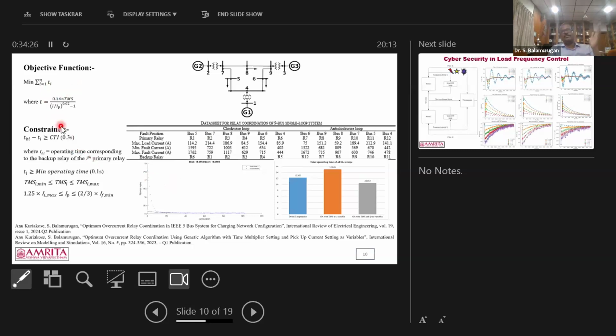So here also we can use an optimization problem. Here our objective function is the primary protection and the backup protection. The total time taken for the primary protection and the backup protection, that I want to minimize. That is our objective function. For the time of operation, the standard inverse curve is considered to be the equation of the relay. And the coordination time, that is between the backup time and the primary time, we consider to be 0.3 seconds. The minimum and maximum TMS setting are considered as inequality constraints, and another inequality constraint is the fault current. One is 125% of the load current and the other is 2/3 of the minimum fault current. That is what is considered to be the minimum and the maximum limit for the fault current on each line.